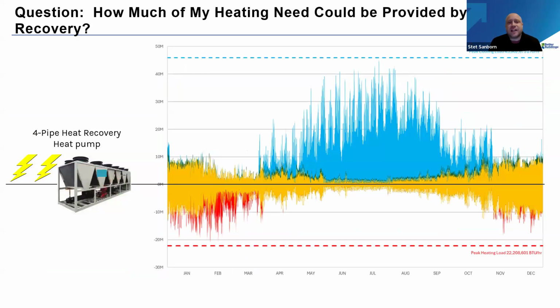And I say that because a lot of times when we look at profiles like this or other buildings, we're bumping up against an electrical capacity issue. And folks are asking, well, how can I still decarbonize even if I don't have enough capacity to meet those short incremental peak loads? And that's where thermal storage comes into play.